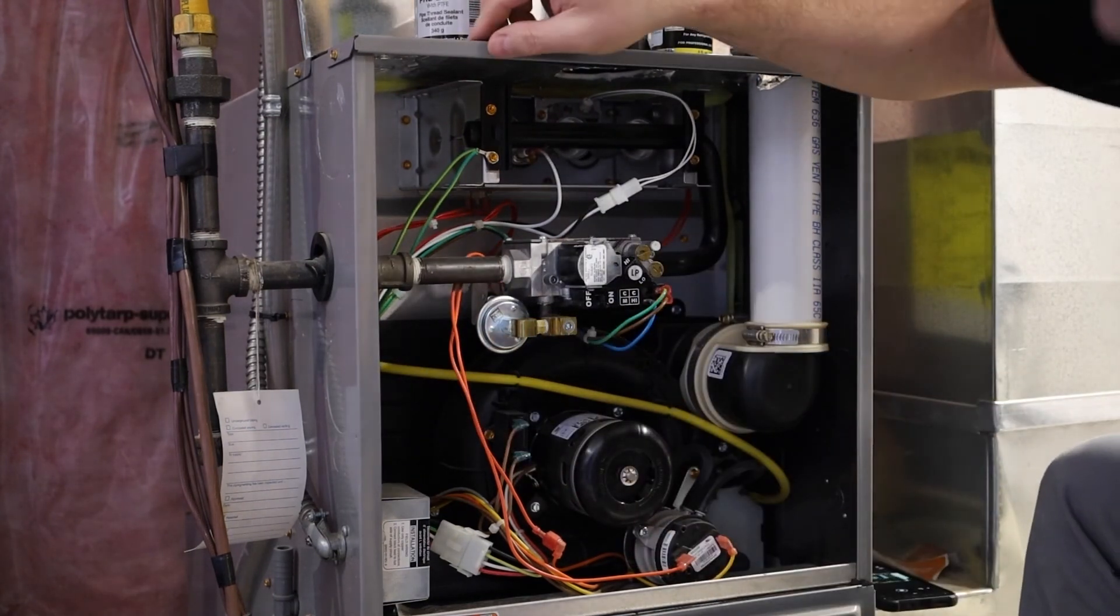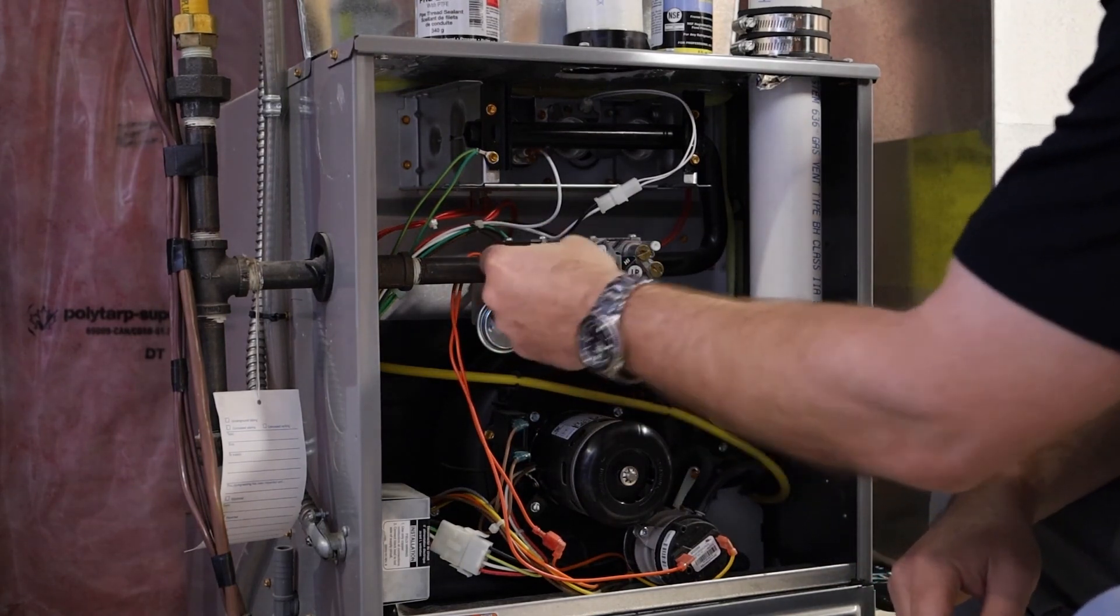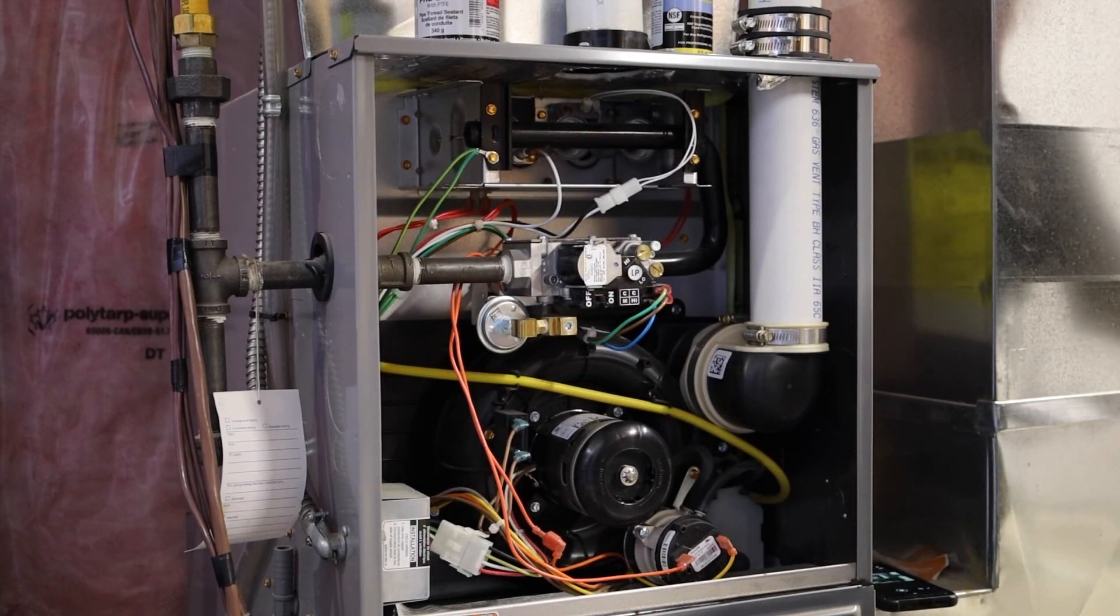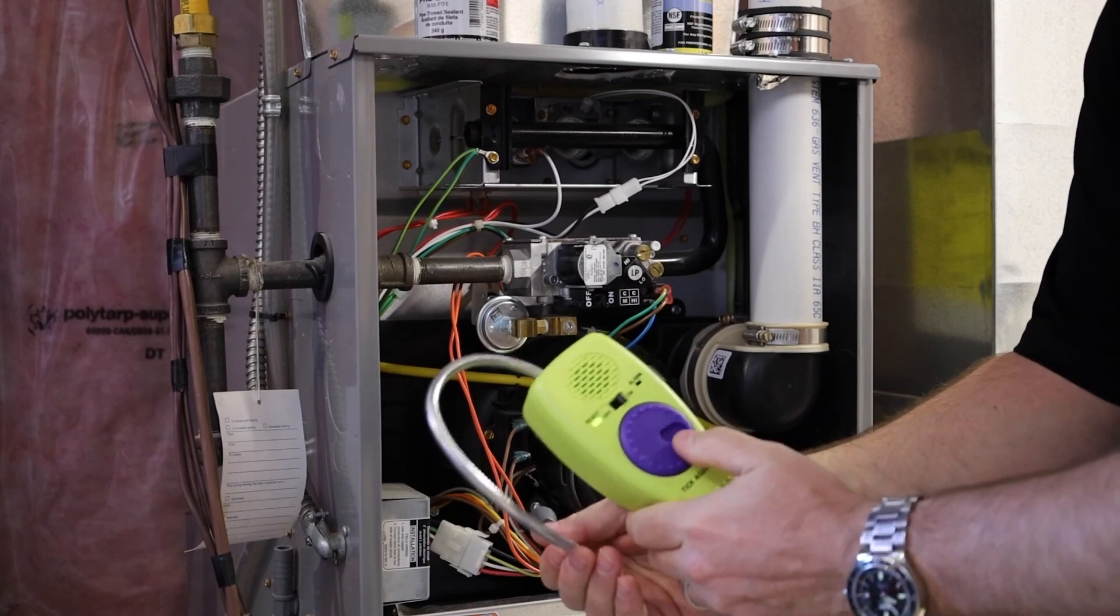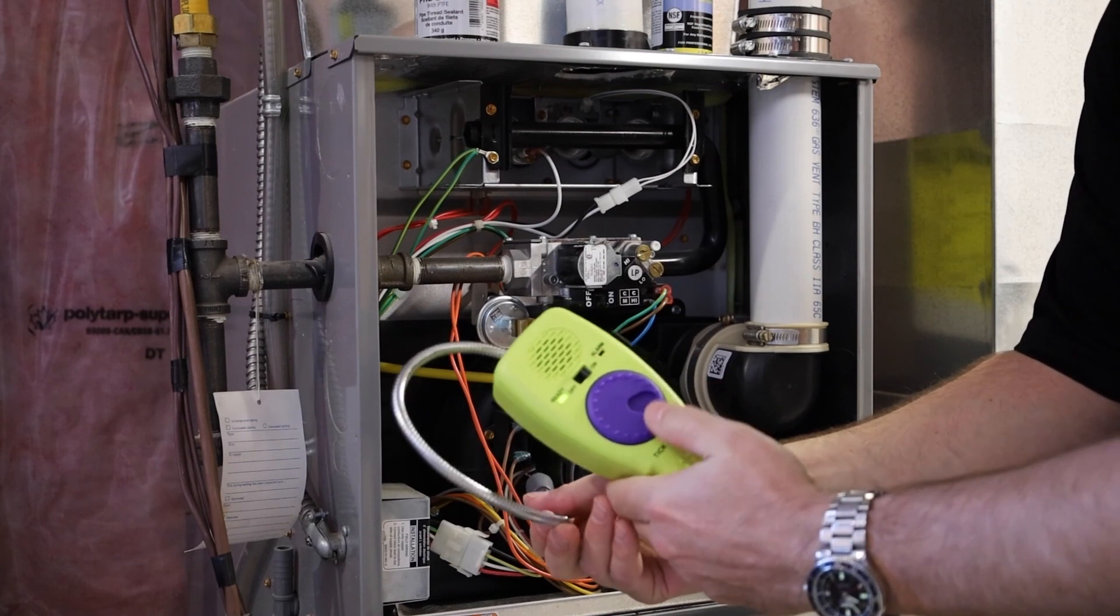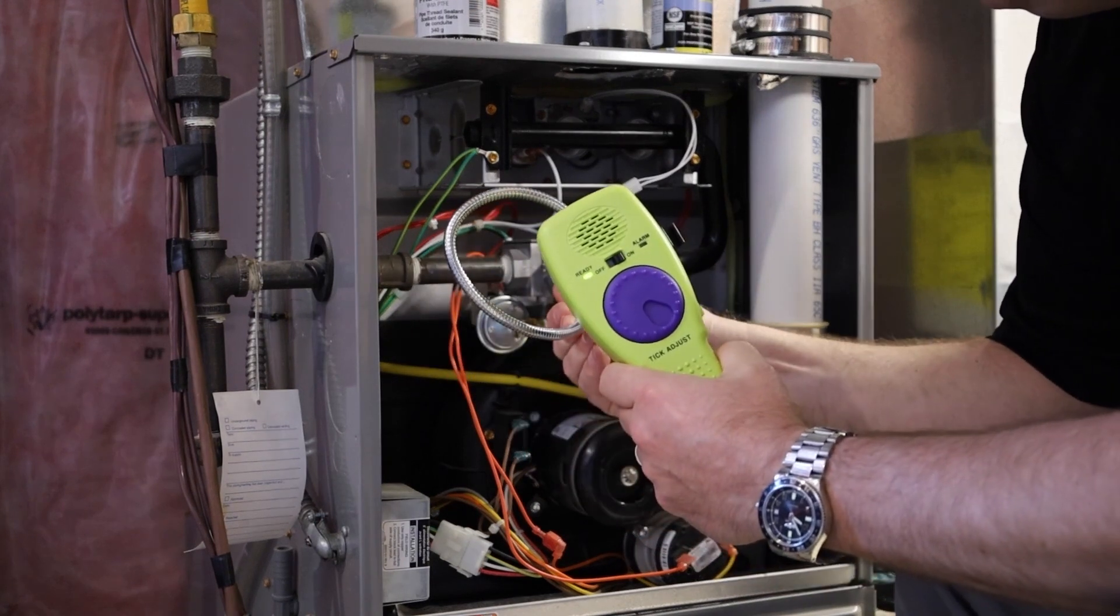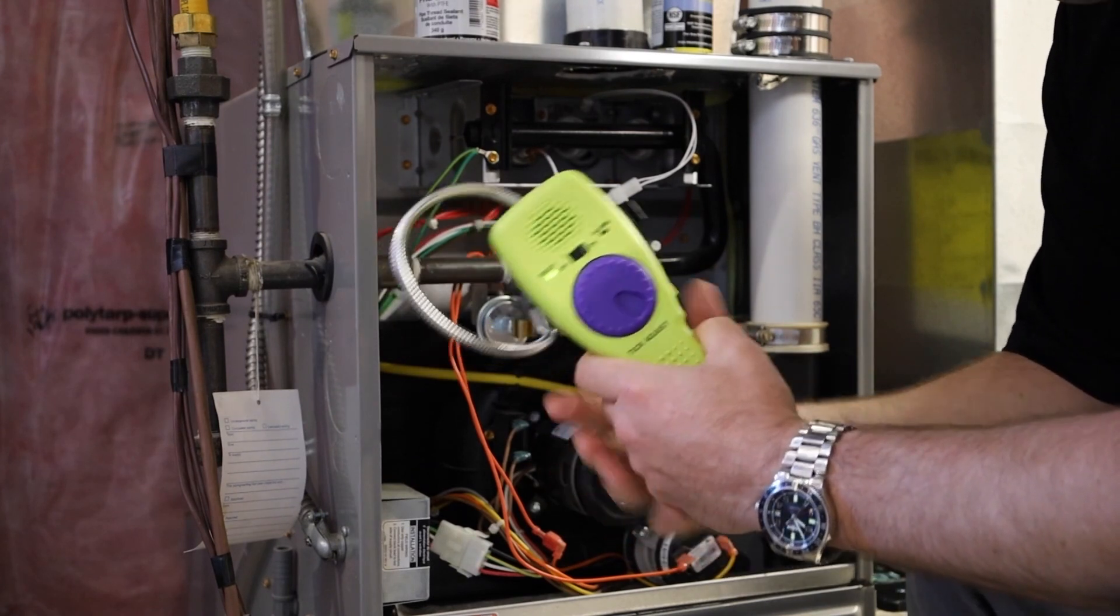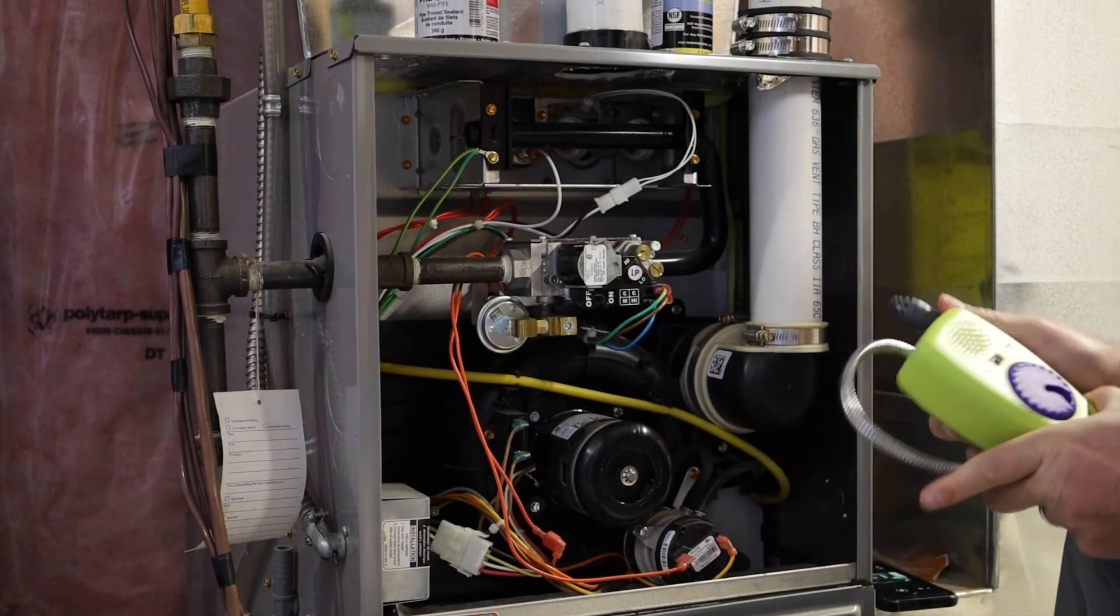Last thing. I'll obviously simulate a leak here. Tighten this up. Using the 720B. Get to my steady state. And I'm going to check for my leak. And I've tightened it up, so of course, there's no leak right there. Safe to put the cover back on.